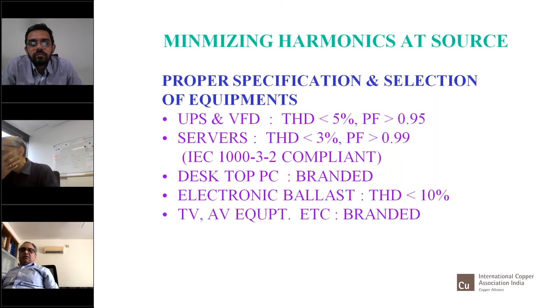Now we come to isolating and arresting harmonics at source. So we need to use special equipment. One I was saying is the UPS. We are putting UPS everywhere for our computers. In every office we have centralized UPS and UPS power supply below every desk. Below every table there are UPS sockets. But nobody is actually aware that this UPS is also arresting the harmonics coming from computers. We put UPS so that we don't lose power whenever there is a power trip, so that the work we have done on the PC is saved and our server does not go down. But this UPS is also a very good firewall. It stops the harmonics coming from all the IT equipment, and on the upstream side of the UPS, the harmonics are reduced drastically.